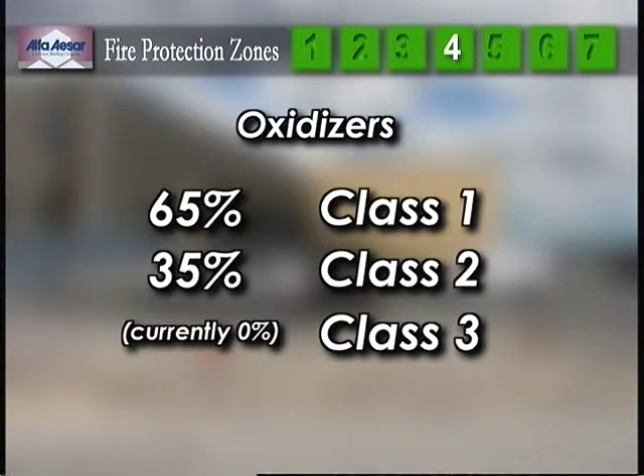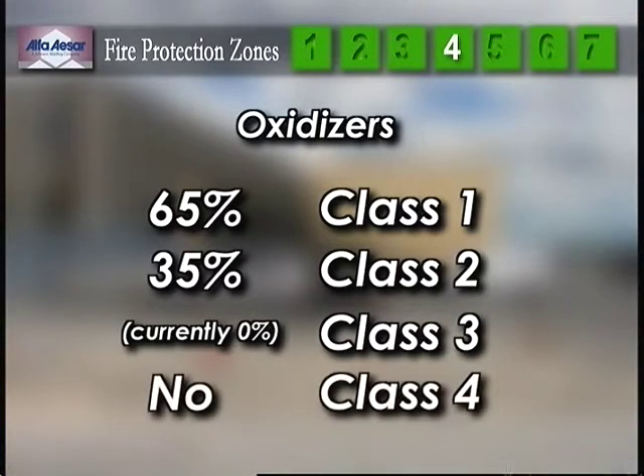These containers are designed to be connected directly to the sprinkler system so that the higher sprinkler flow densities required for Class 3 oxidizers is limited to the storage containers rather than applied to the entire space. No Class 4 oxidizers will be held in inventory at this location.